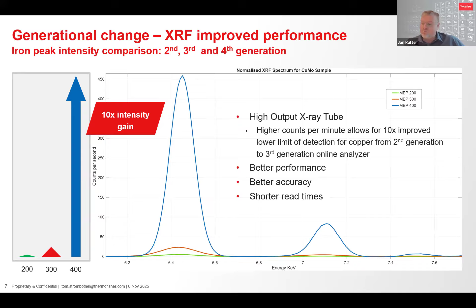So that may include on a conveyor after the primary crusher. That's a great spot before you spend loads of cash grinding waste in the mill. Remember, it's about less waste and more metal. But I suppose the simple why PGNAA can work for you is simple. Air gap and water is basically the enemy of XRF. That's why XRF operates in a slurry where the sample is literally in contact with the XRF analyzer in the slurry sample. But Garry will elaborate more on this for us now.